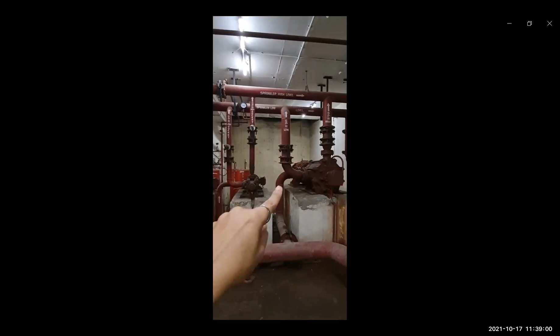First the jockey pump is used, then the low one, and then the high one. Whether it is low or high, it will start pumping with the jockey to maintain the desired pressure level. But when there is more use of water for firefighting, then the main pump automatically starts pumping water to the fire line. Now to operate these pumps, we have these fire panels.